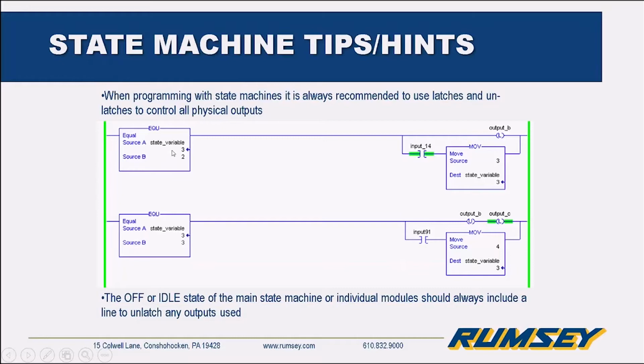In this case, I'm waiting for the state to be in variable 2, turn on the output, get the feedback, move into the next state. If so needed, for instance, if it was an extend, retract on an air cylinder or something like that, unlatch the output before turning on, perhaps, the retract, and then wait for the input to move on to the next state. The main tip then is if you get into the off state or a faulted state, have a step to unlatch these latches before getting back into your program.